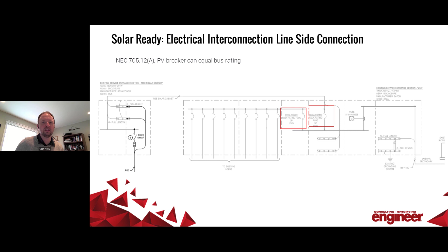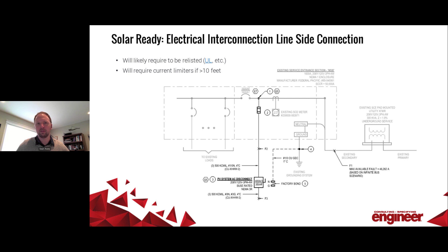In a retrofit scenario, you might have to do a custom bus tap where you drill the bus if you don't have enough existing lugs on the supply side of that disconnect. This will require a UL relisting of the gear generally. You'll probably have to go to a consultant who will come out, take measurements, and determine if and how that gear can be modified to supply the existing equipment.